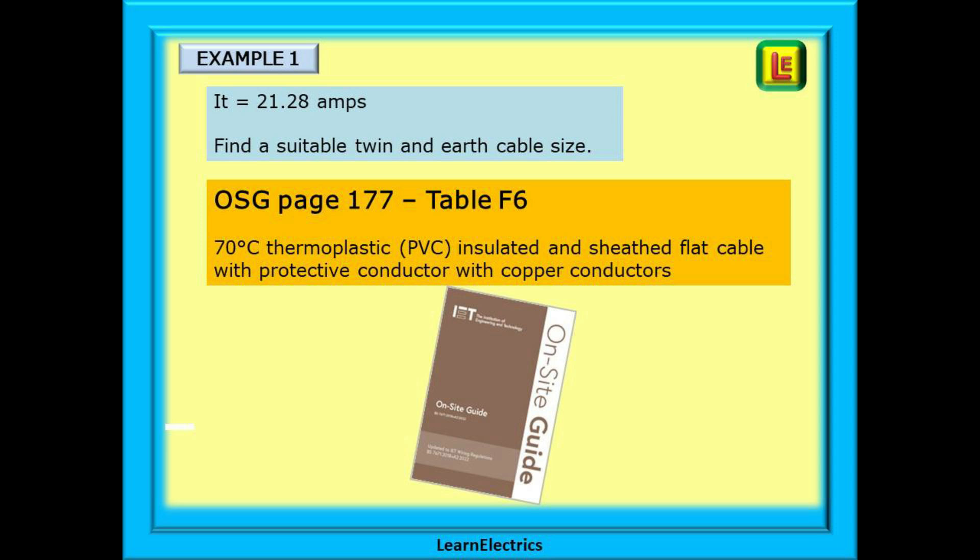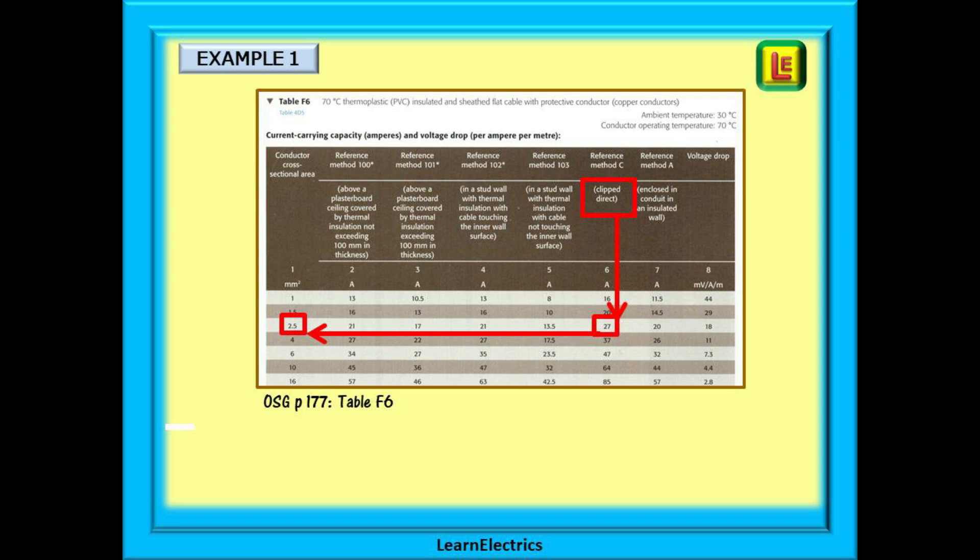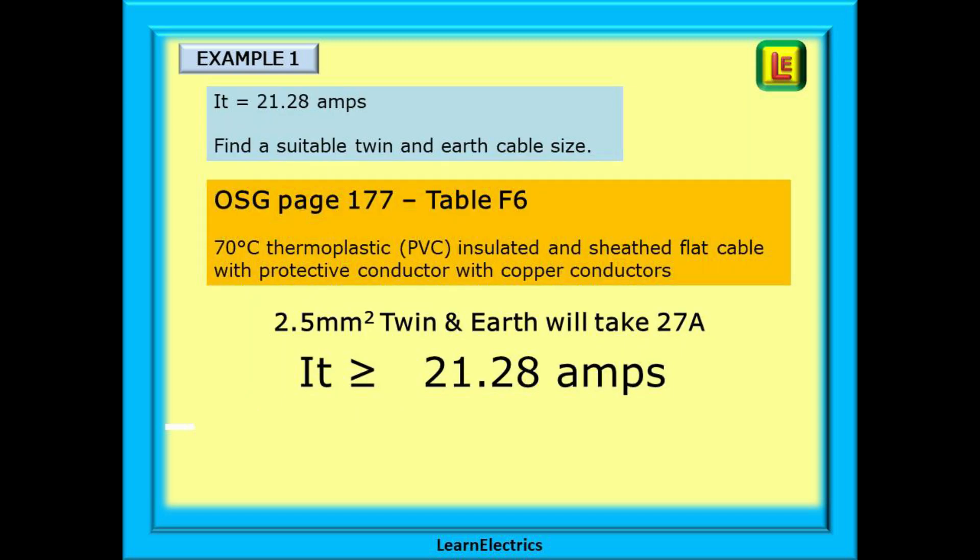Look in the on-site guide, page 177 and at table F6. This table is specifically for 70 degree centigrade thermoplastic, PVC, insulated and sheathed flat cable with a protective conductor with copper conductors. In other words, our standard twin and earth. This is table F6. Find clipped direct along the top, follow the column down until you find a value that is equal to or greater than 21.28 amps. We find this is 27 amps. Now, move to the left and read off the conductor size which is 2.5 millimeters. For this circuit, we must choose 2.5 millimeter twin and earth cable. So, 2.5 millimeter twin and earth would take 27 amps and this means that IT is in fact greater than 21.28 amps. Job done.